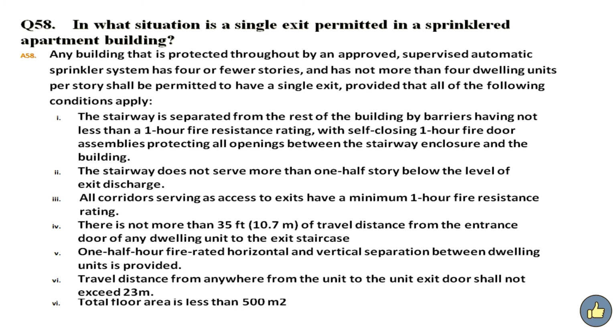Number 2. The stairway does not serve more than 1/2 story below the level of exit discharge. Number 3. All corridors serving as access to exits have a minimum 1-hour fire resistance rating. Number 4. There is not more than 35 feet, 10.7 meters of travel distance from the entrance door of any dwelling unit to the exit staircase. Number 5. 1/2 hour fire rated horizontal and vertical separation between dwelling units is provided. Number 6. Travel distance from anywhere in the unit to the unit exit door shall not exceed 23 meters. Number 7. Total floor area is less than 500 square meters.